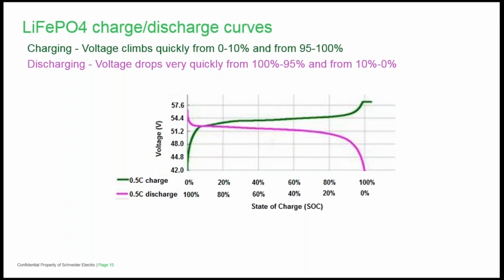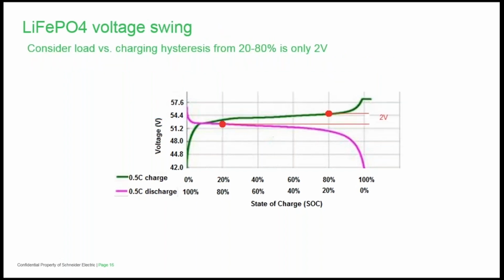Note how little the voltage varies from 20 to 80%. It's almost flat. Notice there's only a difference of about 2 volts when charging at C/2 and discharging at the same rate. If the charge-discharge curve for lithium iron phosphate was linear, it would be much easier to approximate state of charge from voltage. Unfortunately, the voltage is almost flat between 20 and 80%, making it very difficult to approximate state of charge from voltage alone.